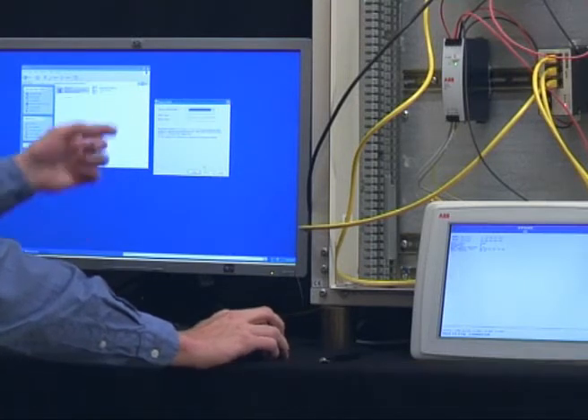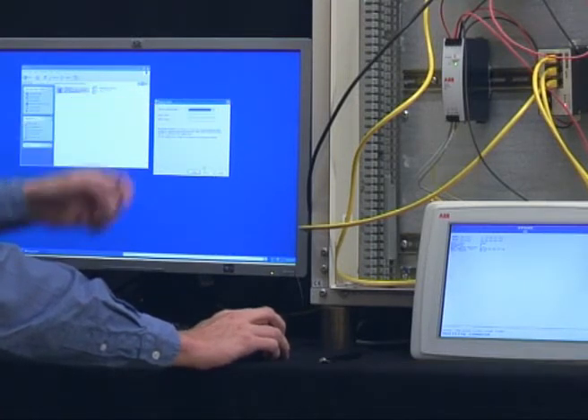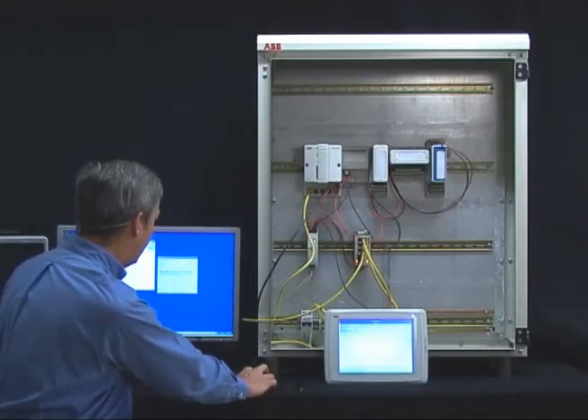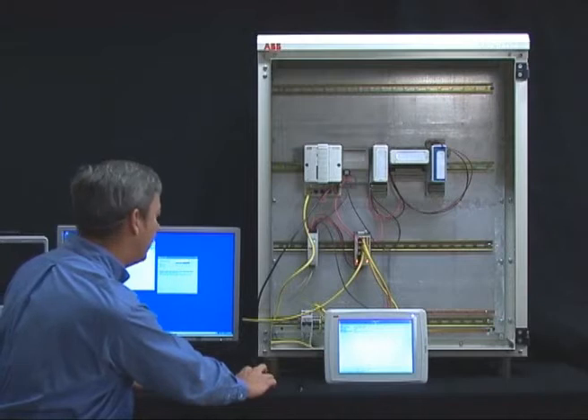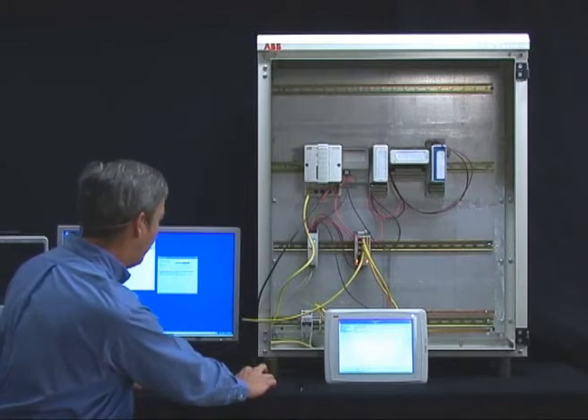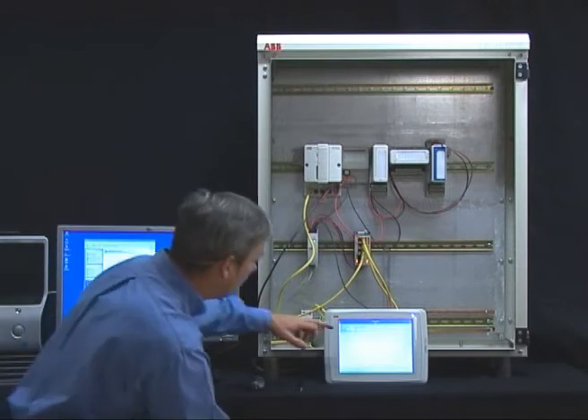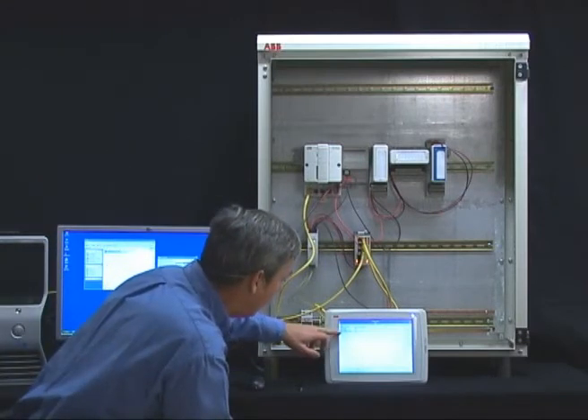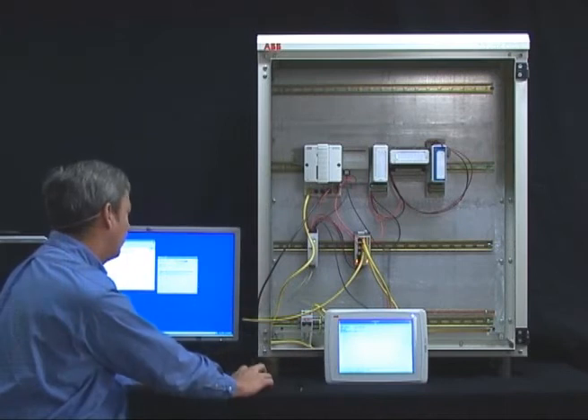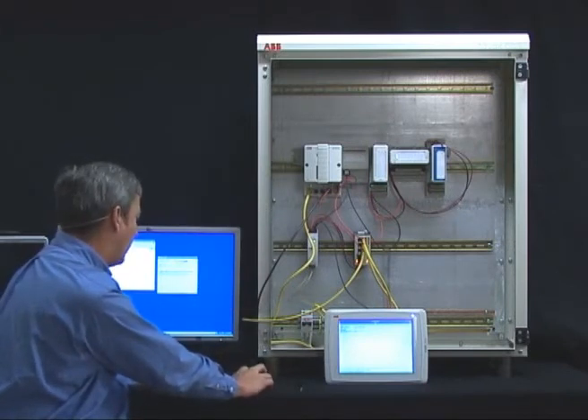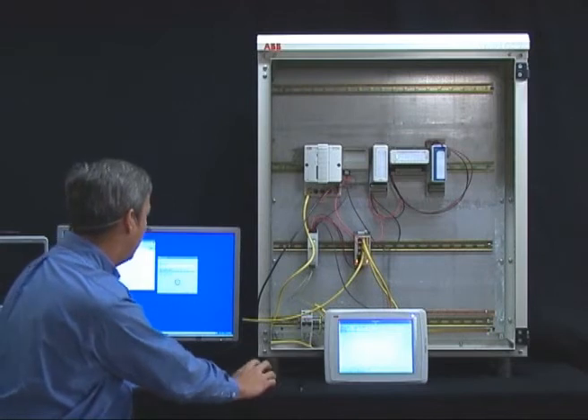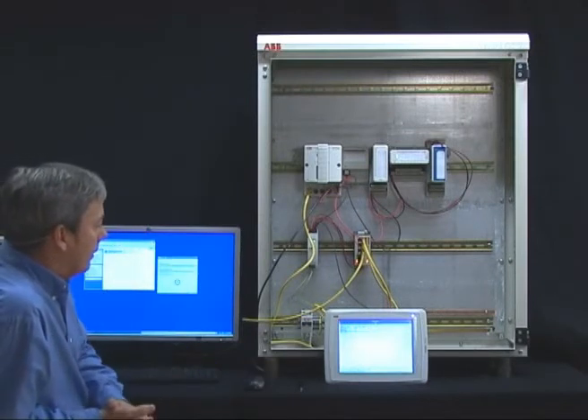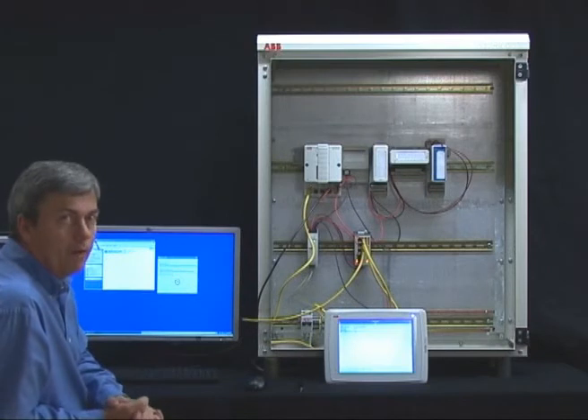When we press next, we can see that we have a selector box where we can select operator terminal. If we click on that, we can see the MAC address of the panel that we would like to download firmware to. If we want, we can also look at the panel here and see that we have the same MAC address displayed on the panel. Then we press upgrade and now the panel is receiving the new firmware.